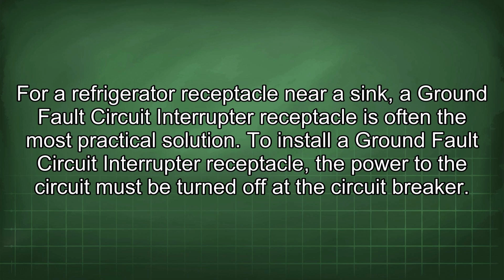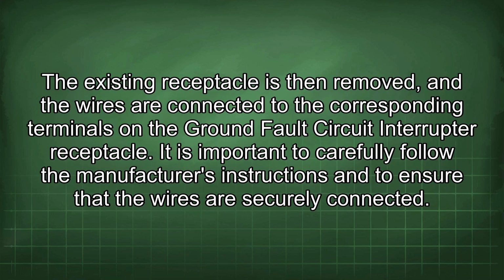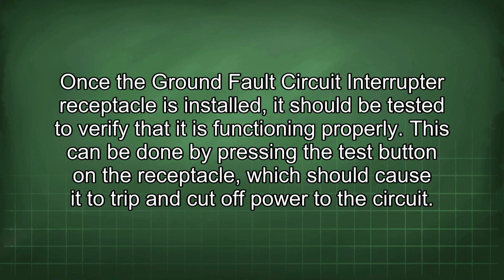To install the ground fault circuit interrupter receptacle, the power to the circuit must be turned off at the circuit breaker. The existing receptacle is then removed, and the wires are connected to the corresponding terminals on the ground fault circuit interrupter receptacle. It is important to carefully follow the manufacturer's instructions and to ensure that the wires are securely connected. Once the ground fault circuit interrupter receptacle is installed, it should be tested to verify that it is functioning properly. This can be done by pressing the test button on the receptacle, which should cause it to trip and cut off power to the circuit.